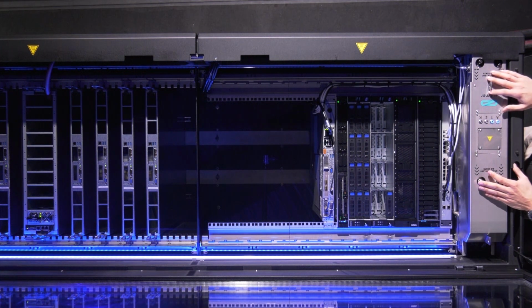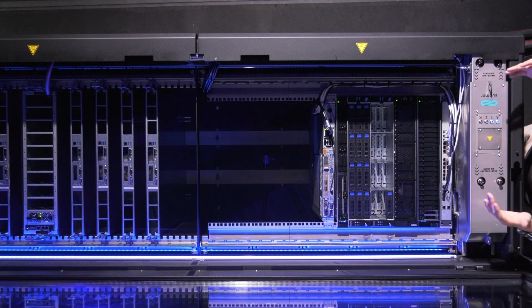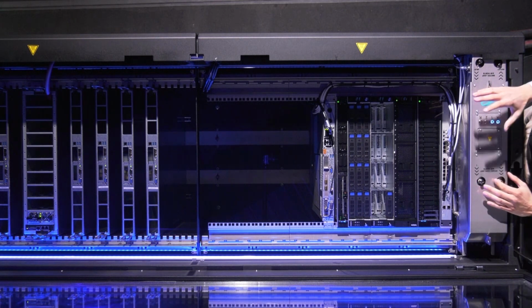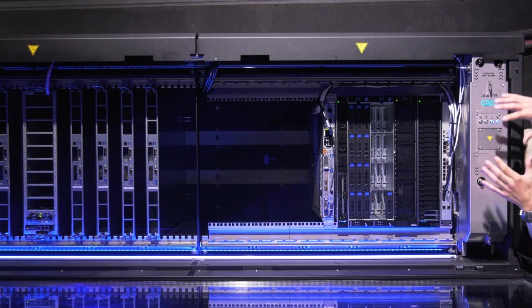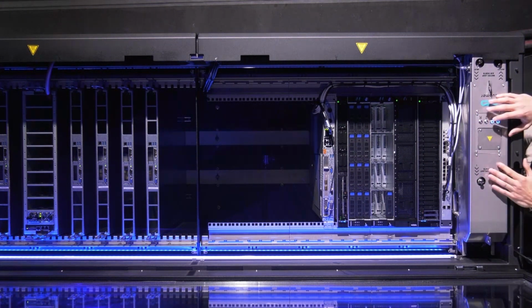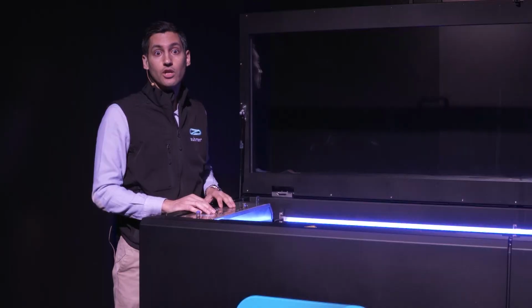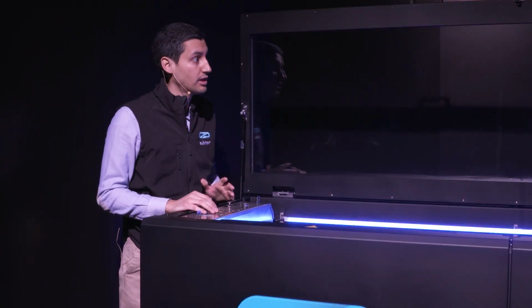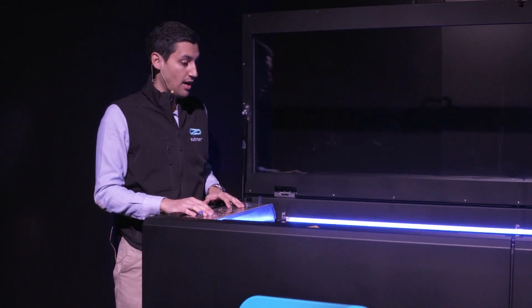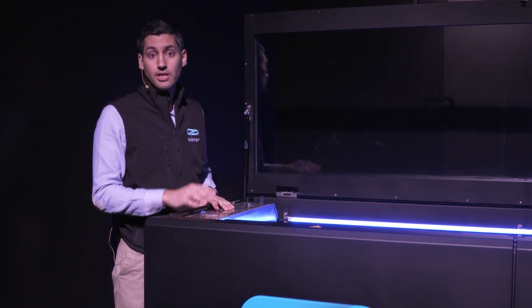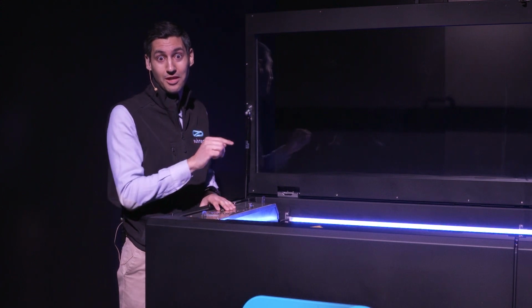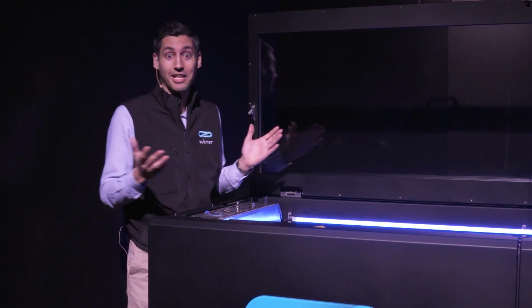We don't use moving parts, we don't need fans, so we optimize not only the facility PUE, which is 1.03, but also the IT usage effectiveness. Normally, 10 to 25% of the electricity is wasted by fans within the server, so it doesn't make any sense.